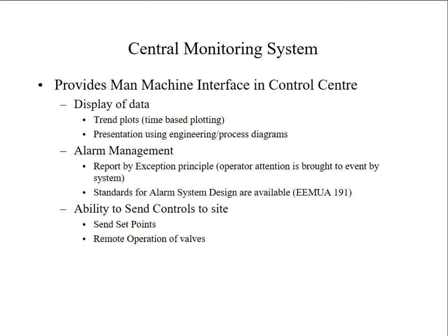Anyway, it'll allow you to open or close valves, maybe for special operations, for example, or it might be that you want to divert flow this way rather than that way. For overall operational purposes, optimization in the sense of overall process optimization, you might be closing, but it's not about safe operation. You're not relying on this system to provide the protection.